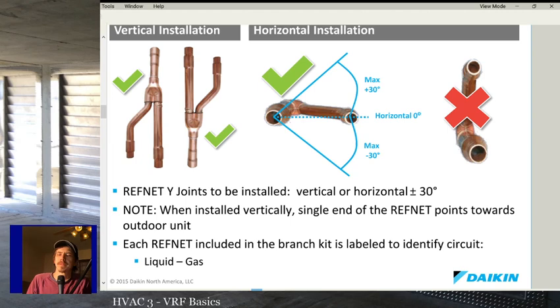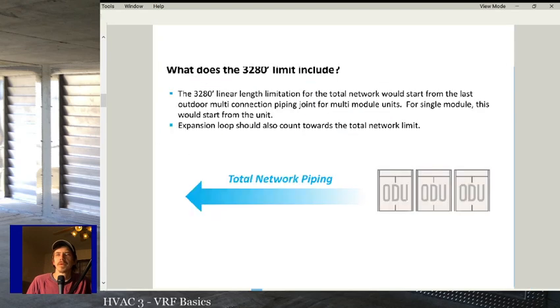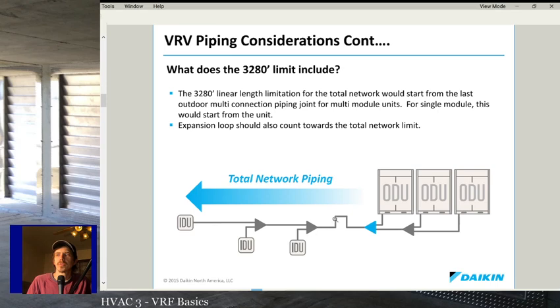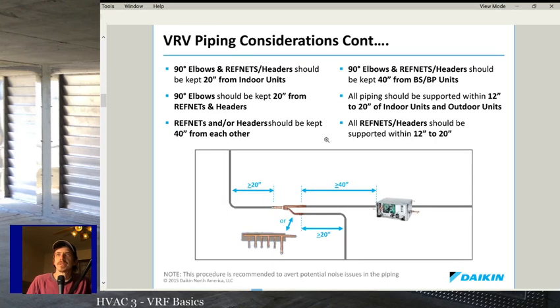Now, that's most of the quick and interesting things when it comes to the piping. Like I said, there are a bunch of rules here. There's length limits. There's distances. Like I said, pretty much like it's talking about here. Elbows and headers should be kept 20 inches from indoor units. You generally just say 2 feet.